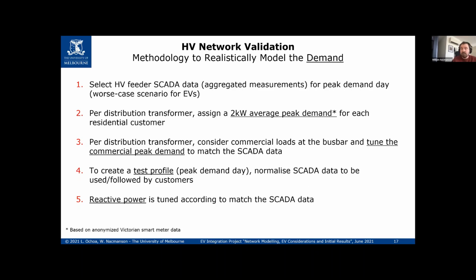We want to think, okay, what's the worst case scenario for electric vehicles? Well, it's when there's a lot of demand. So we look at the peak demand day and gather up our information for that day for our feeder. Then for each distribution transformer in the HV feeder, we assign an average peak demand for each residential customer.